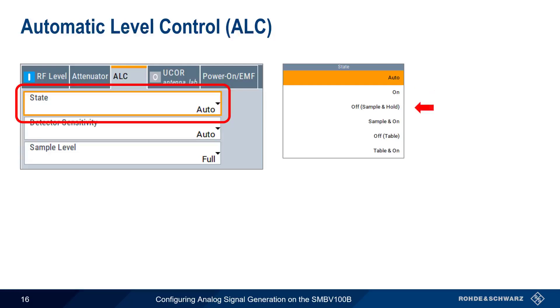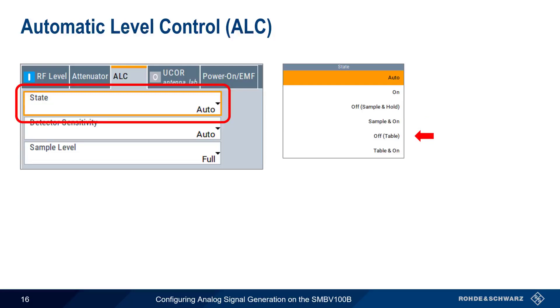In OFF SAMPLE and HOLD, the SMBV switches briefly into CW mode, enables ALC to adjust and save the level, and then turns OFF the ALC. SAMPLE and ON does the same thing, but without disabling ALC. The last two ALC states involve an internal table. Remember that ALC is a control loop, so the output is based on the history of the signal. OFF TABLE uses an internal table, rather than the history, to control the attenuation values. TABLE and ON starts with the attenuation settings from the table, and then activates automatic level control. This improves setting times when something in the RF path changes. In the case of pulse modulation, this mode ensures fast level setting even with narrow pulses at low repetition rates.